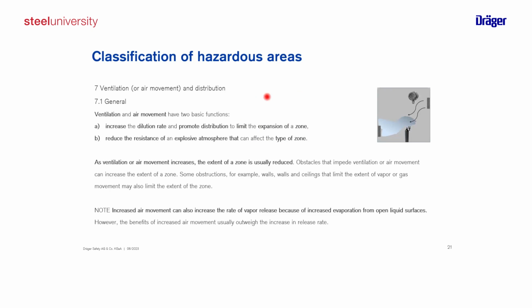The other is by using ventilation, you can classify an area as a zone. And if the ventilation is an active measure, you can also declassify or bring it to a lower level. So instead of having a zone 1, you have a zone 2. Or if your ventilation is perfect, you can also bring it to a non-zone. Important is always you need to consider how the air movement is inside, and if you have blockages or any kind of obstacles which could mean that the gas release we are faced with has no chance to escape, or we can't detect it. So important is to consider what are possible air movements, air streams, ventilation, all these, as this has a direct impact on how our explosive atmosphere or gas will vaporize in the room.